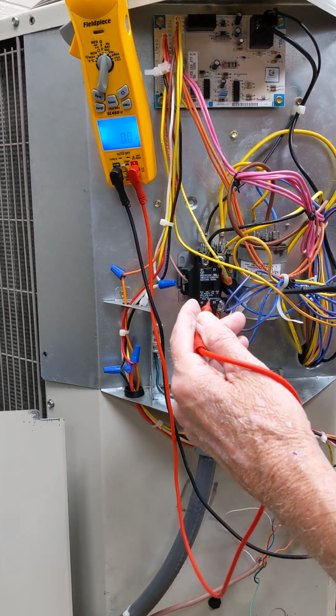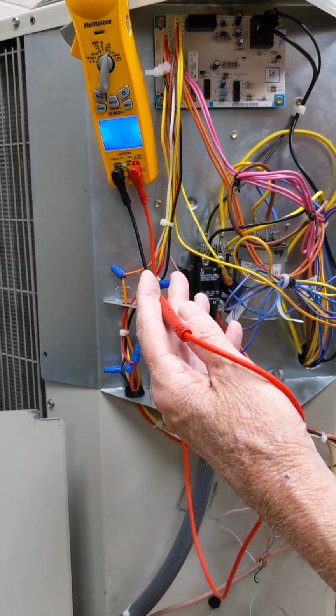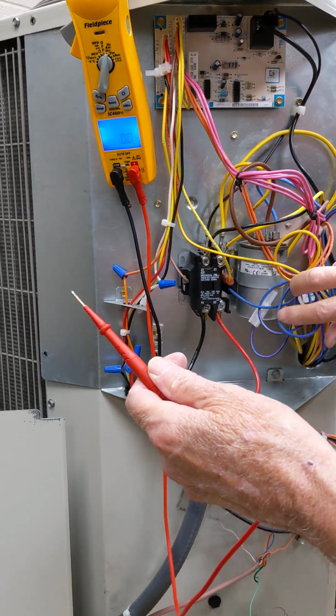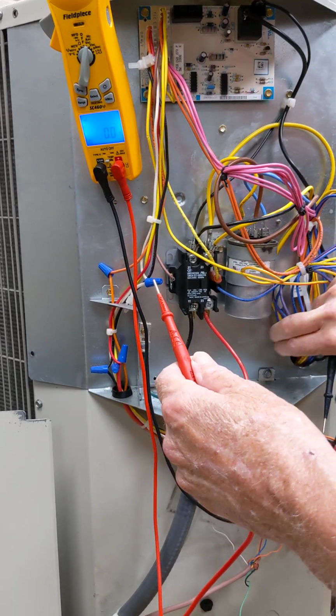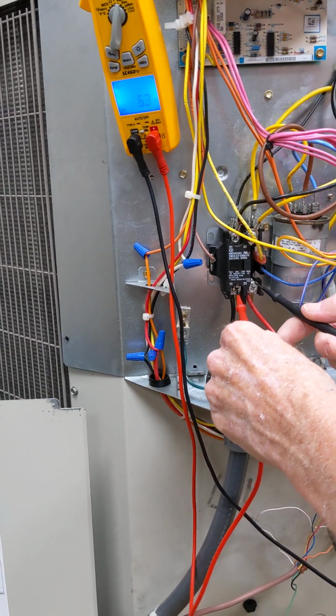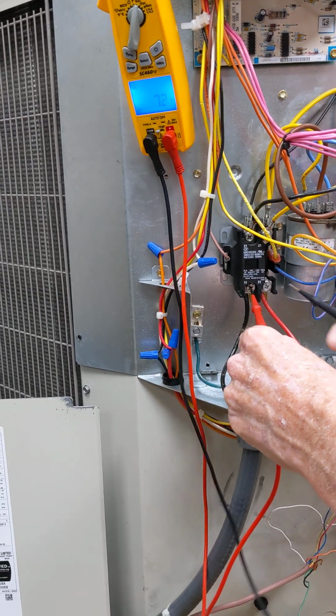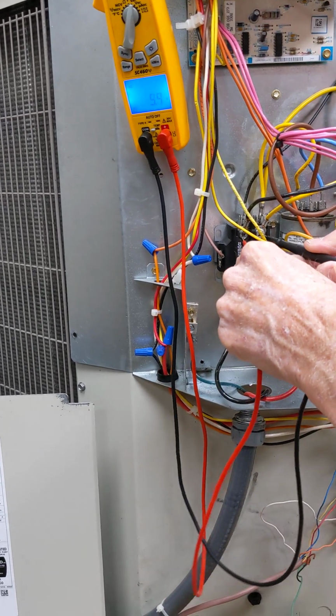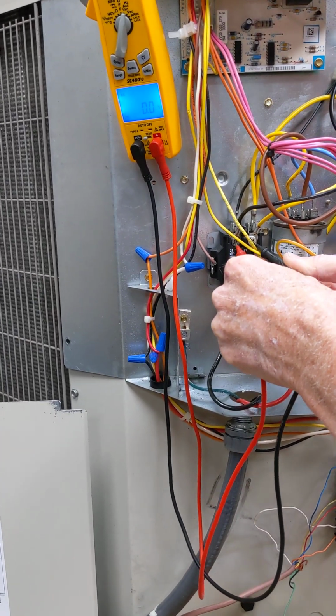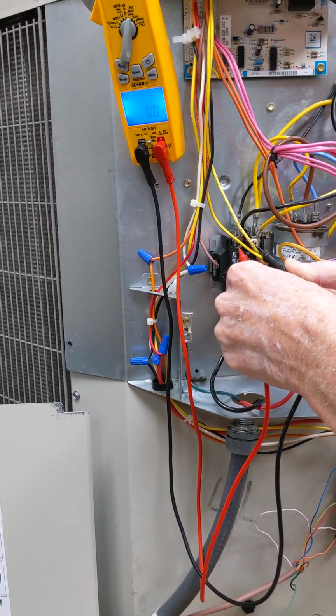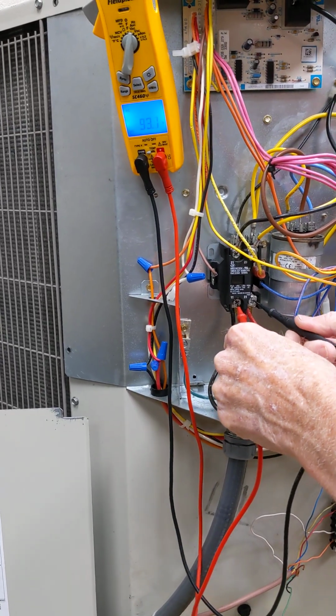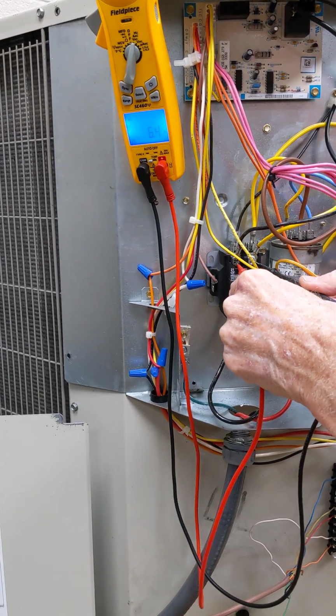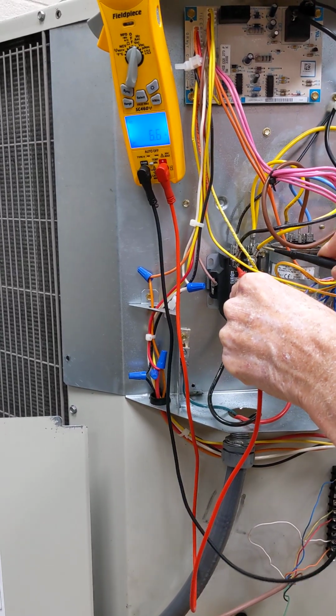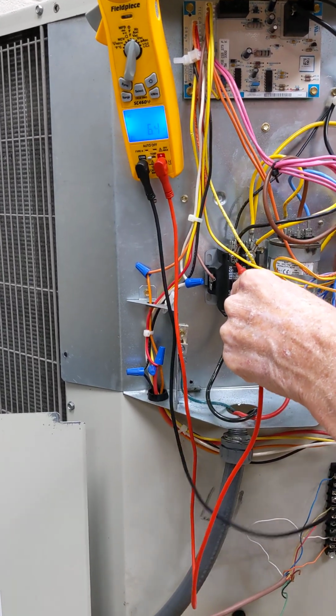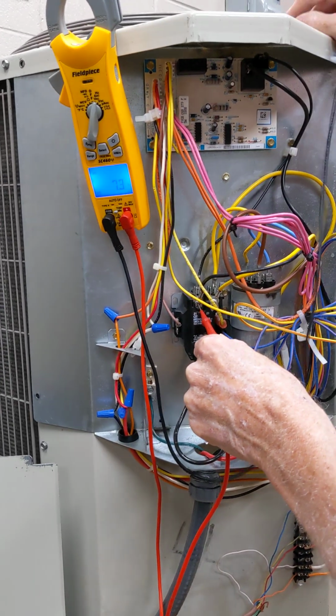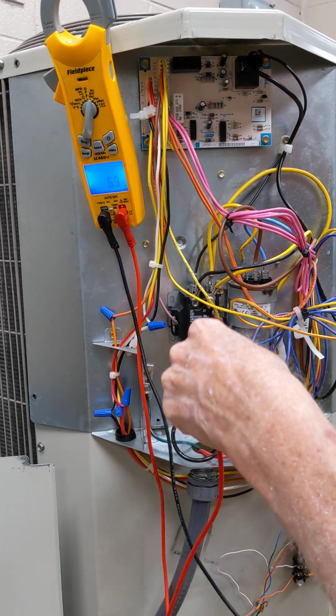That's why I have nothing, okay? So I don't have a call for the machine to run. But I still have high voltage on here. And here's what I want you to be careful with, is this right here. If I test this, yes, I have the 240 and I can do that to ground. I can do this side to ground. But this says up on the top, I have nothing, right? Nothing. I have 240 coming in, but I don't have it going out. So I should be safe to touch any of this stuff, disconnect this stuff, disconnect it from the capacitor, take off the lid, pull the motor out, but it's not.